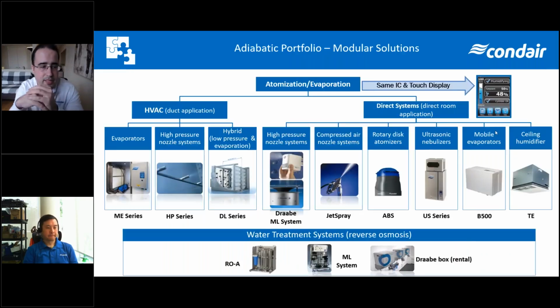We have lots of products in the adiabatic range, and we're primarily going to focus on the adiabatic products. On the left, we have media systems and spray systems. We also have hybrid systems, mostly ceramic with an atomization system. Then we have in-space systems: high pressure, compressed air, rotary. We also have small in-space applications like ultrasonic, mobile evaporators, and a ceiling humidifier, also evaporative. So we have different types of applications, from very big loads to very small loads. And we also have an in-house water treatment system, from reverse osmosis for very small systems to very large systems.